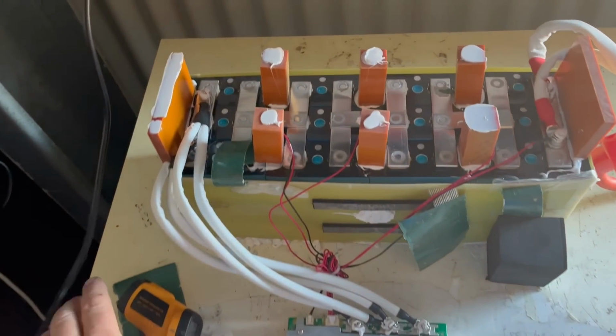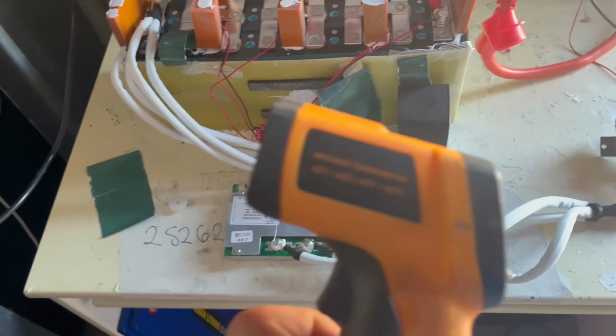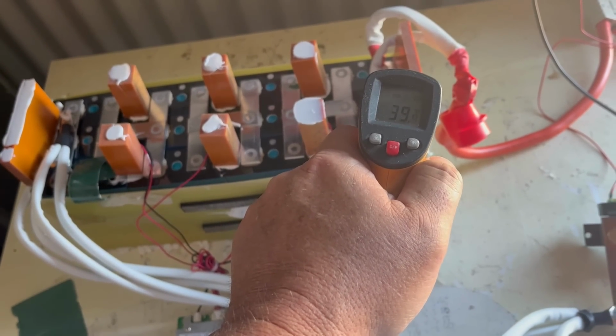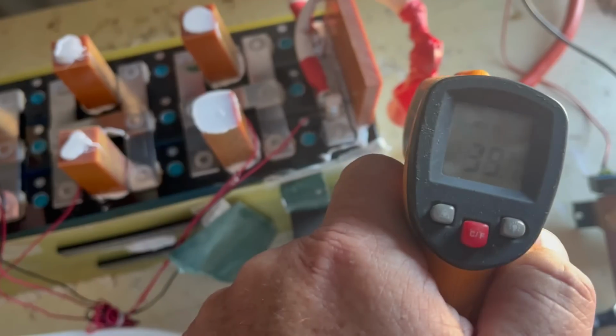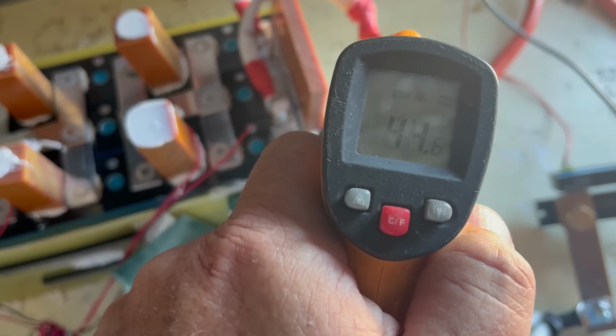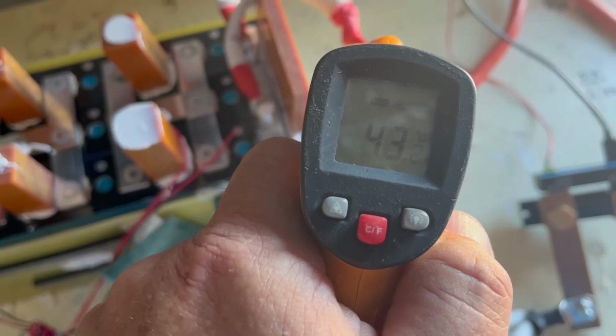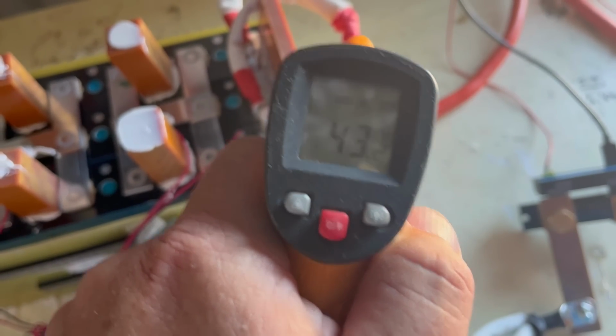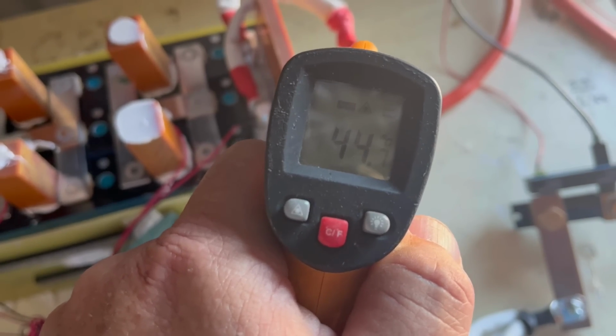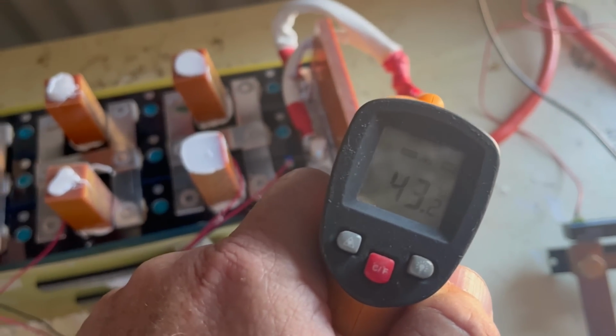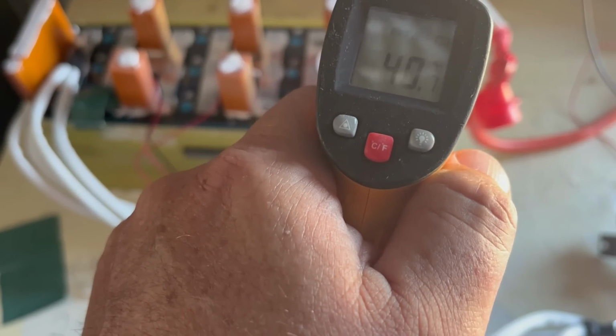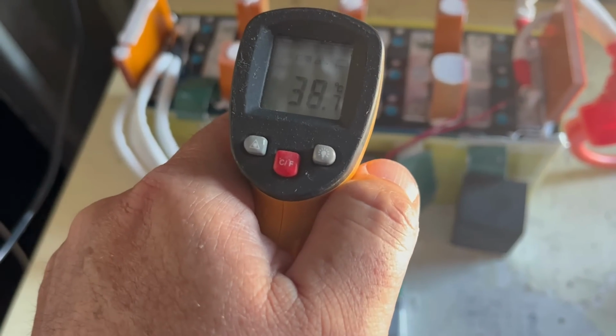So look, if you want to satisfy your own curiosity, get yourself an infrared heat gun like this and check your terminals. Look at that, normal working 40 degrees, 44 degrees. It shouldn't be any more than 40 to 50 degrees. When it was hitting over 70 degrees, there's obviously a problem. And it showed in the video that there's a loose terminal. Everything else looks pretty good.